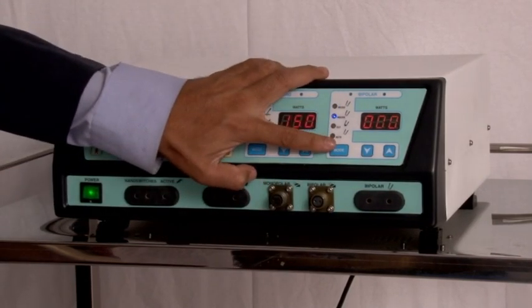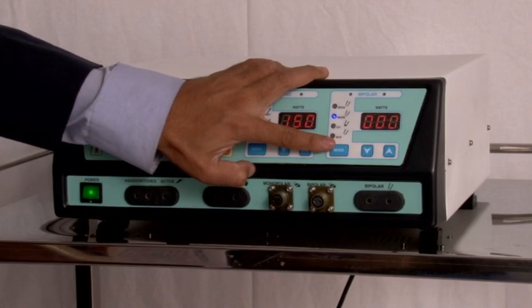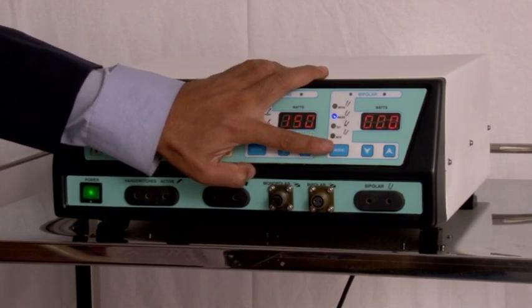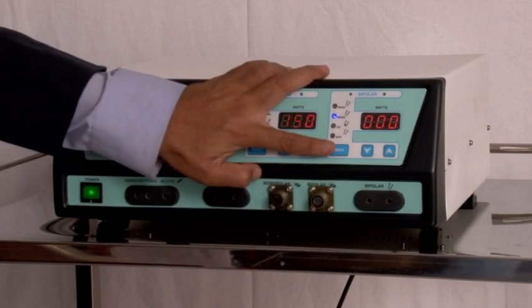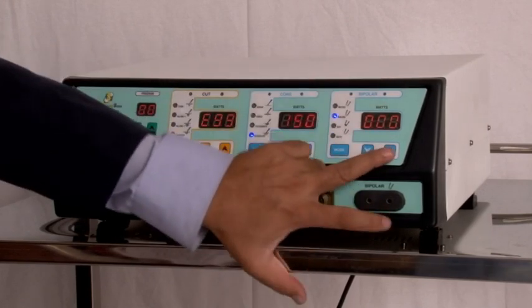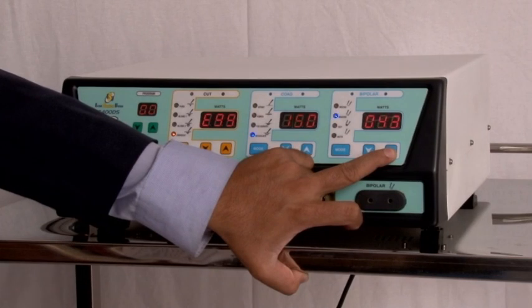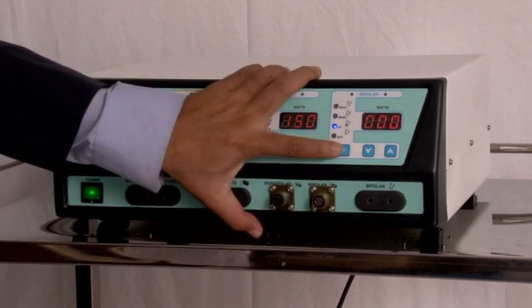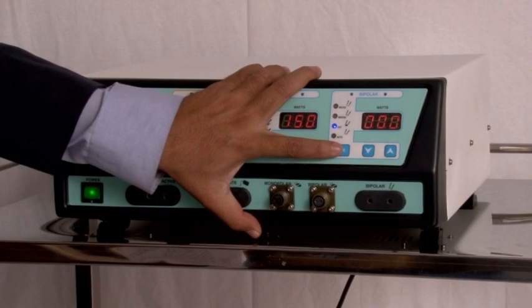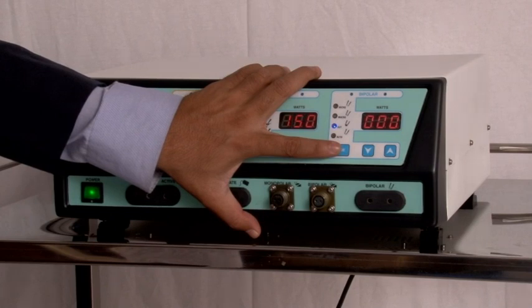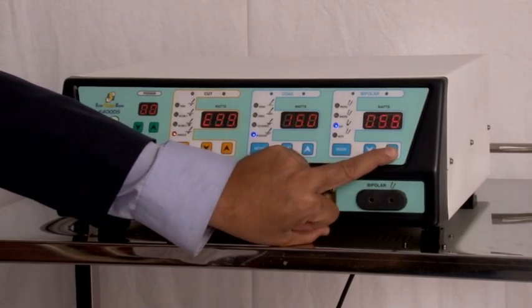Second mode in bipolar is macrobipolar, a pure sinusoidal waveform with increased voltages, which assures rapid coagulation and is used in all types of surgical procedures. Macrobipolar has a maximum output of 80 watts. Third mode in bipolar is bipolar cut. It gives constant cutting effect over all types of tissues. This output is designed for special instruments used in advanced endoscopic procedures. Bipolar cut has a maximum output of 100 watts.